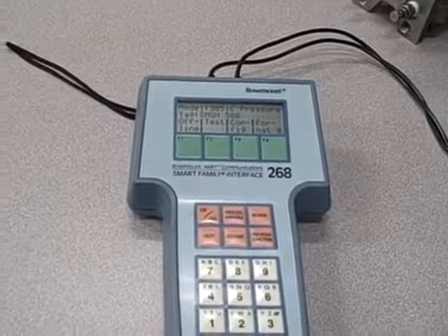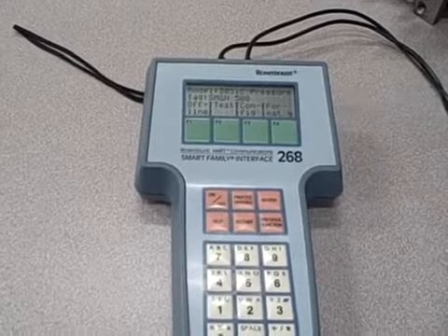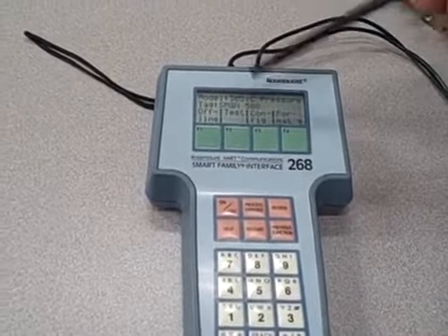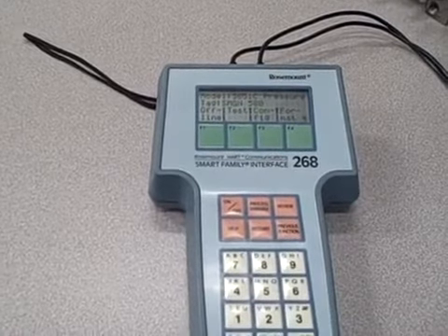device description file. Now in some cases, if my DD file in here is so old, it won't even talk to the transmitter at all. It won't even be able to tell, for instance, that it's a 3051C pressure transmitter. So that can happen as well.